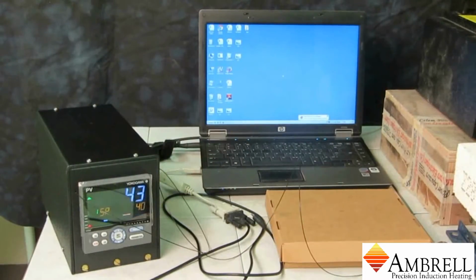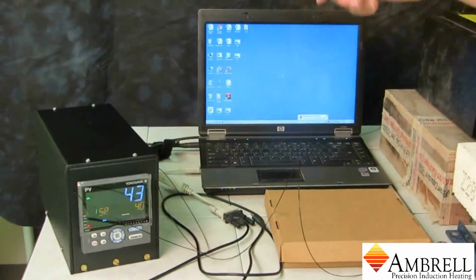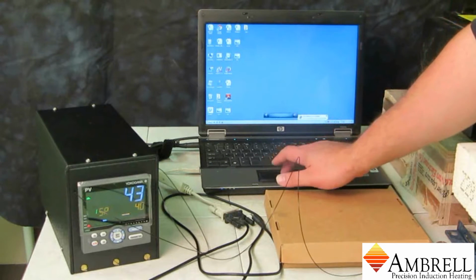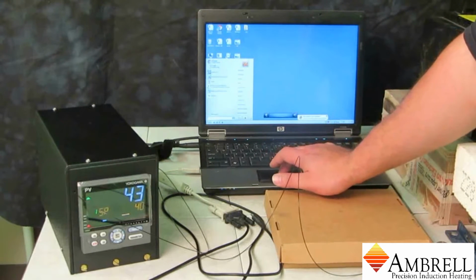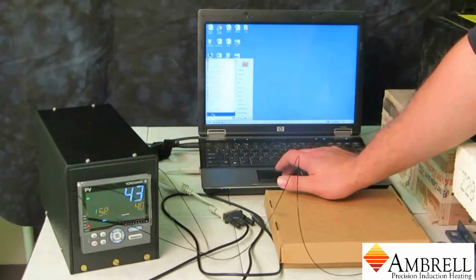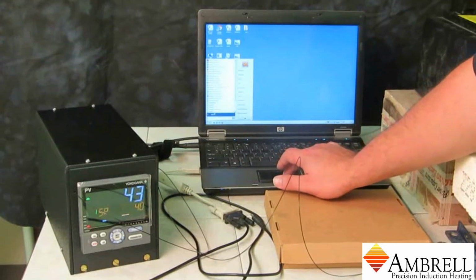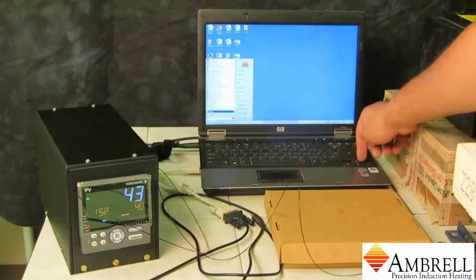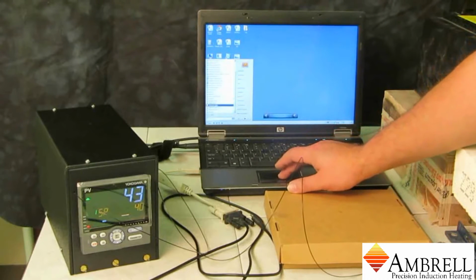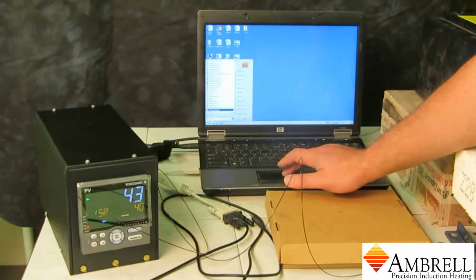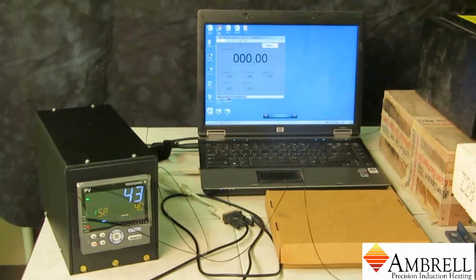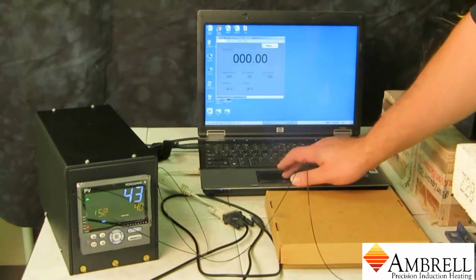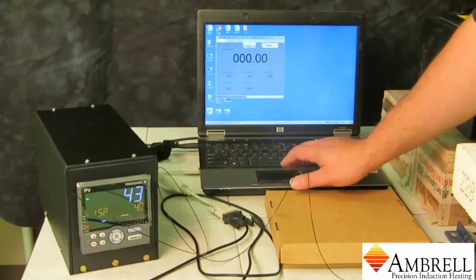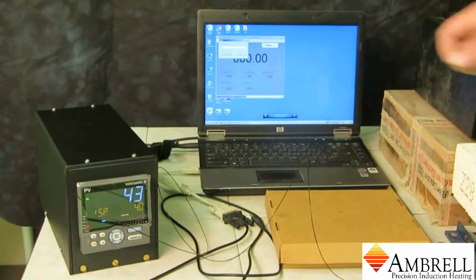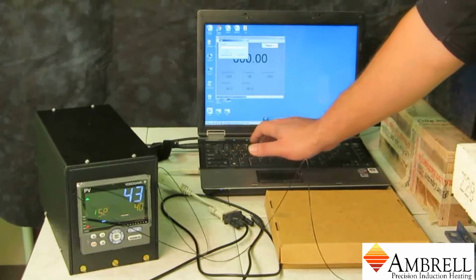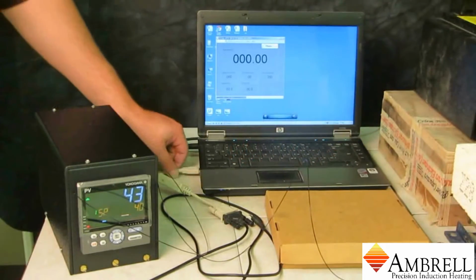Now, here's the setup. You'll notice that the Yokogawa unit believes that room temperature is 43 degrees Celsius. That's because the Photon control box needs to be properly scaled. So, we need to go into the Photon control software, go to the Help pull down, and go to Login. So we'll do that in a moment, and the password is user, which we'll enter momentarily. Alright, the password was just entered.